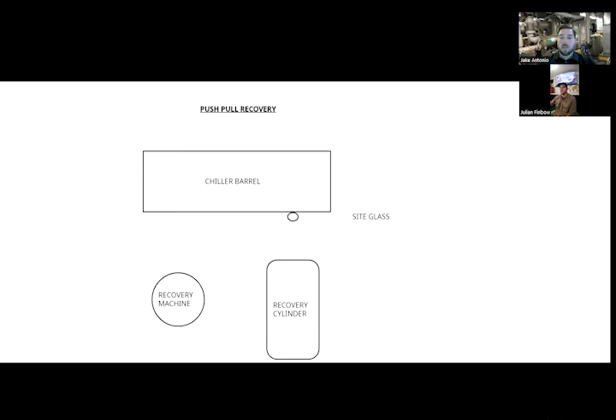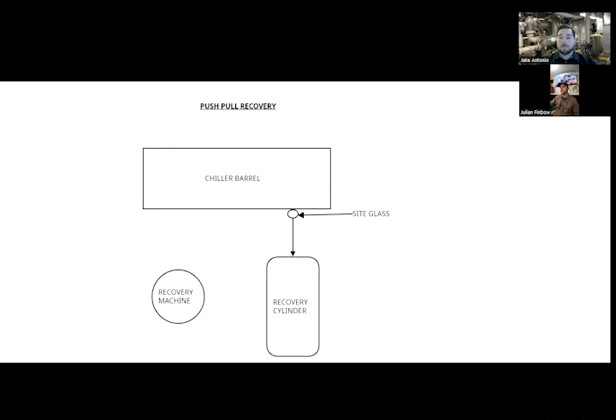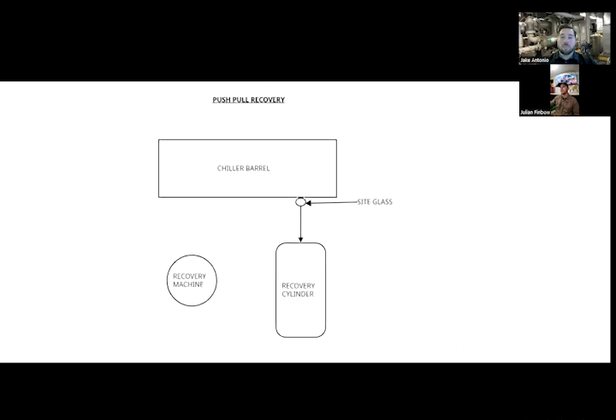The reason for the sight glass is so that you can see the liquid coming out, so you're going to have a valve there and sight glass, and you're going to hook up right on the bottom of the chiller. Then you're going to take your 1/2 inch hose and hook it up to the liquid side of your recovery bottle.